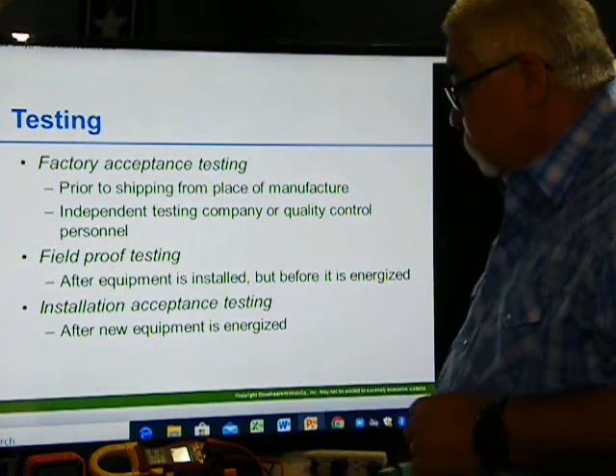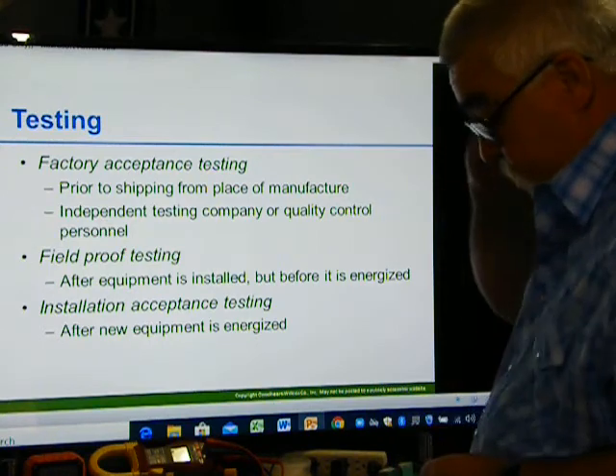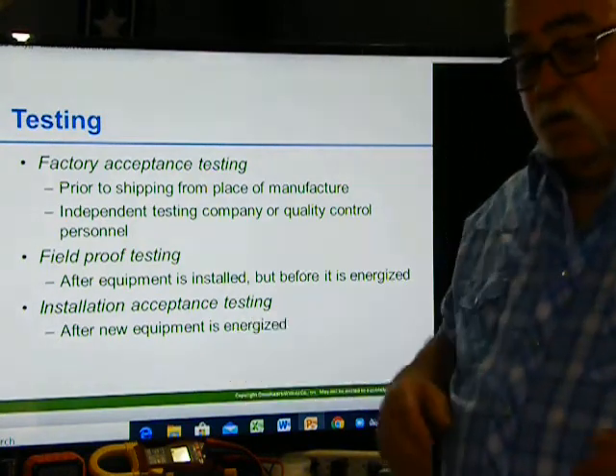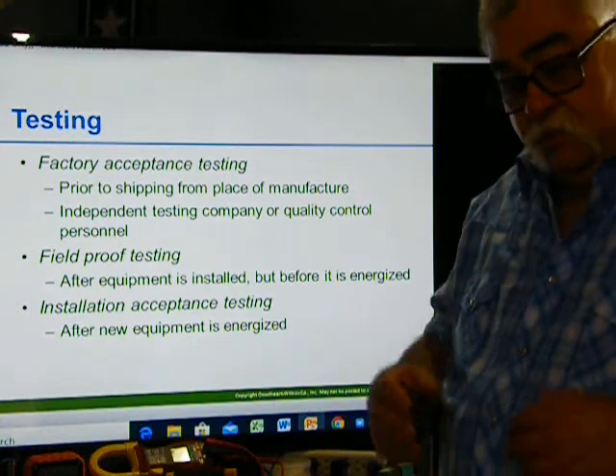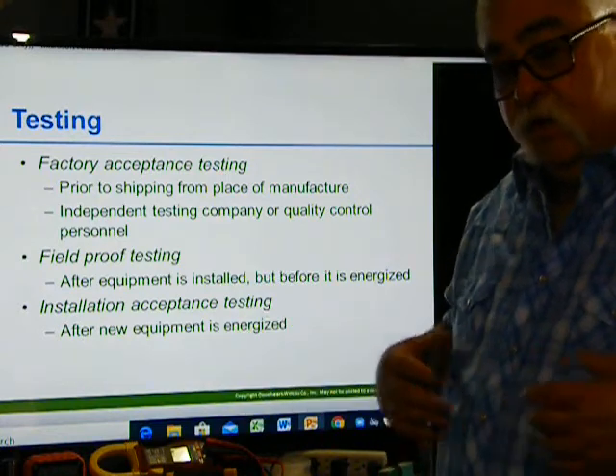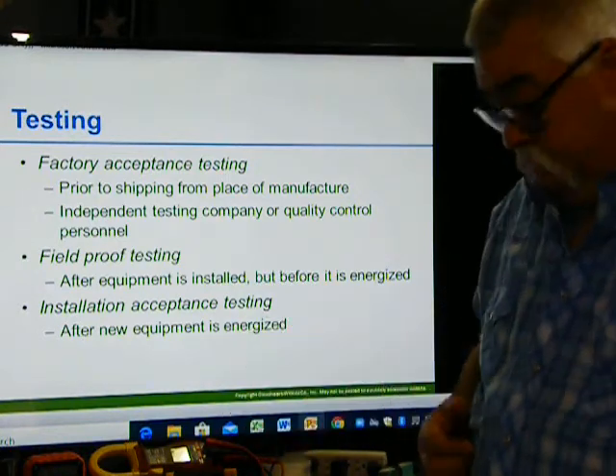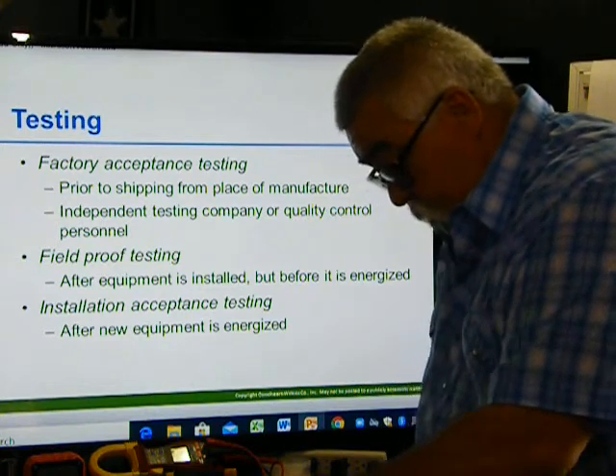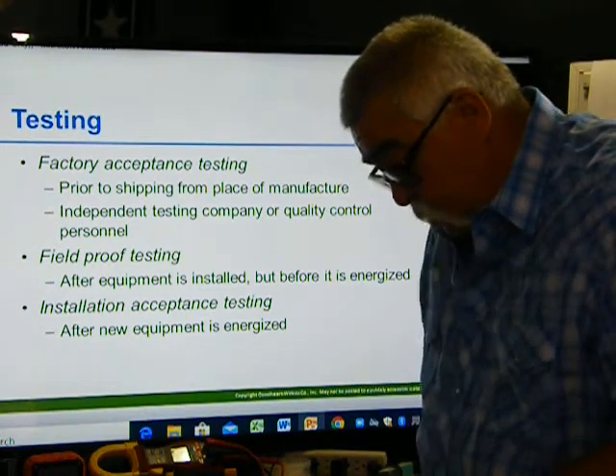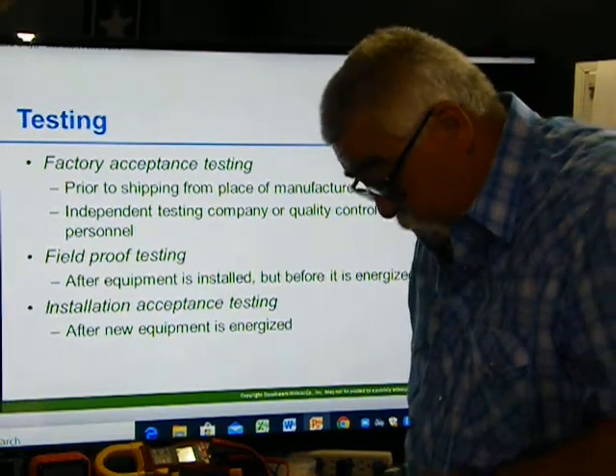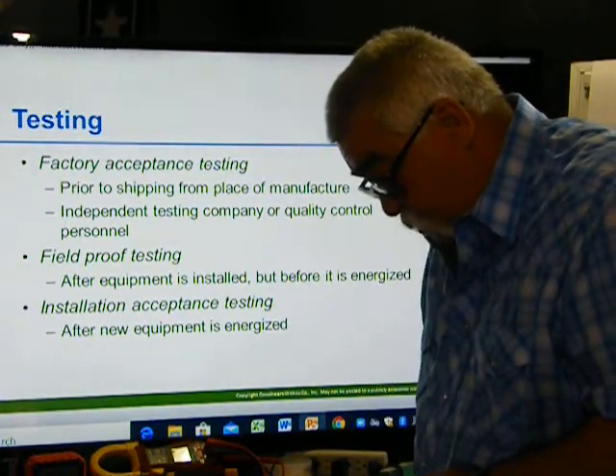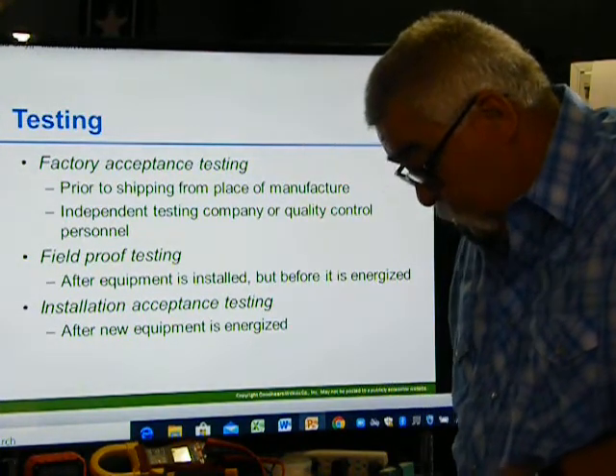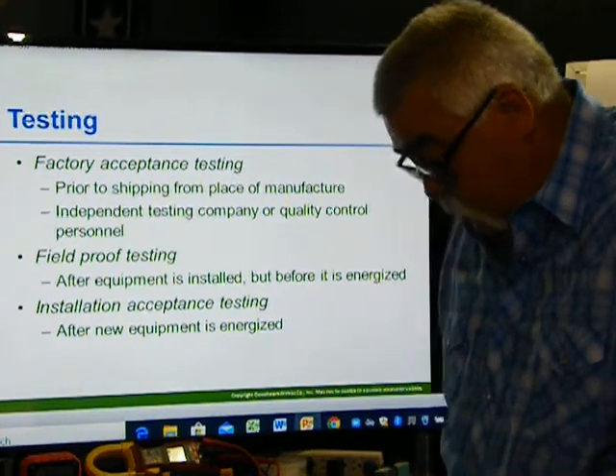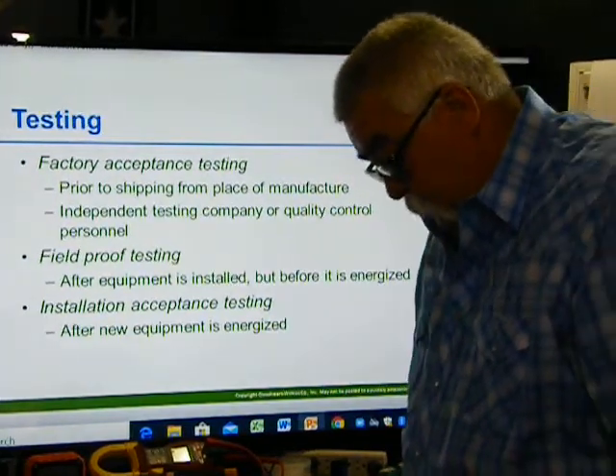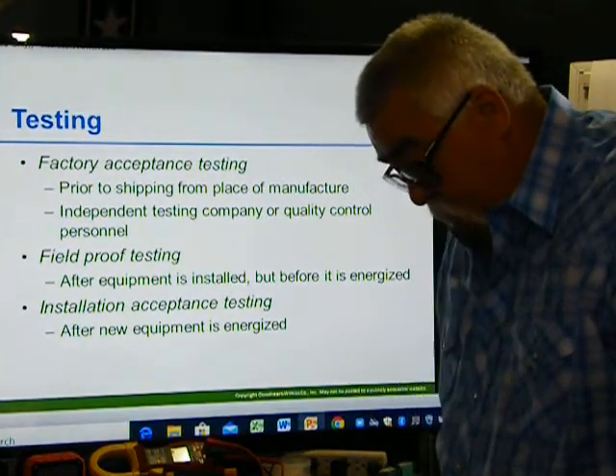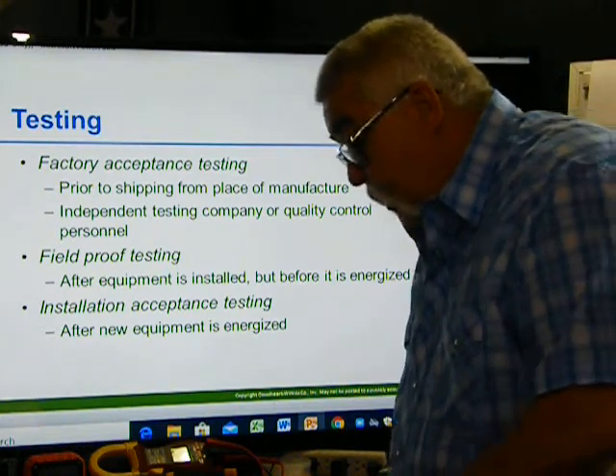Installation acceptance testing is after new equipment is energized. So now they get it installed. Now they did a test run. They checked everything. They feel everything is good. Now they turn it on. So installation acceptance is similar to field proof testing, except these tests are done after the new equipment is energized. Data recorded at the initial stage is saved for future use. Initial test readings establish excellent baseline comparison data.